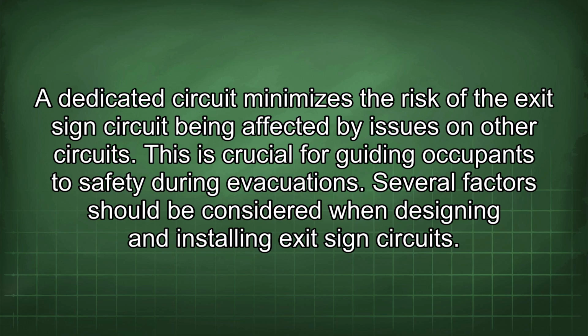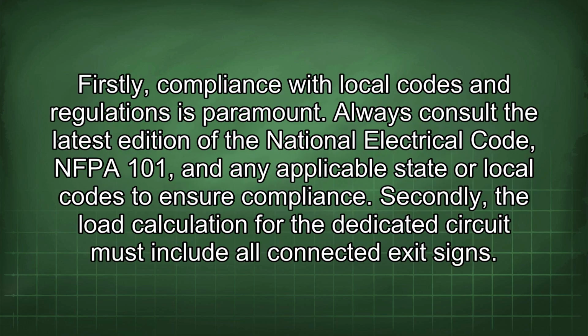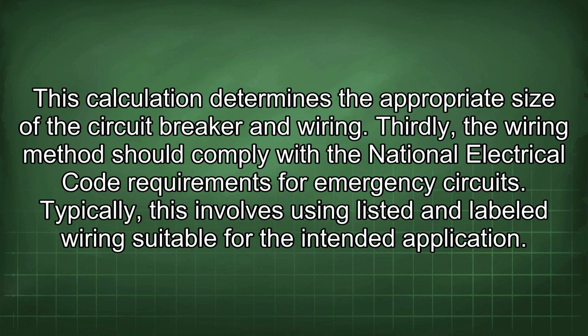Several factors should be considered when designing and installing exit sign circuits. Firstly, compliance with local codes and regulations is paramount. Always consult the latest edition of the National Electrical Code, NFPA 101, and any applicable state or local codes to ensure compliance. Secondly, the load calculation for the dedicated circuit must include all connected exit signs. This calculation determines the appropriate size of the circuit breaker and wiring.